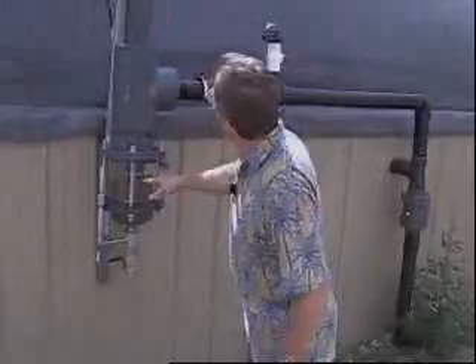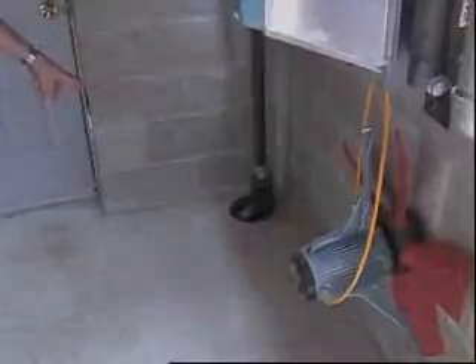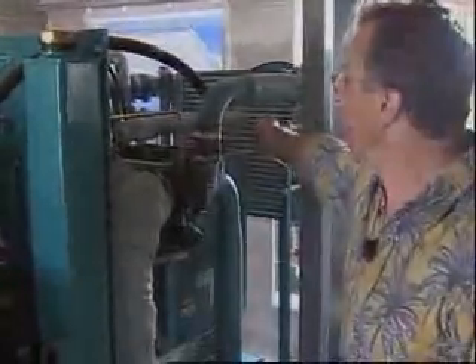The valve has opened now, and here we lose methane gas because the balloon is full, and we really should start the generator. Here the methane gas comes in into the generator. Here we measure the volume of the gas with a meter. And then it goes up here to the turbocharger, where the gas gets mixed with air. It goes through the cooler — the after-cooler of the turbocharger — and comes in here into the diesel engine.